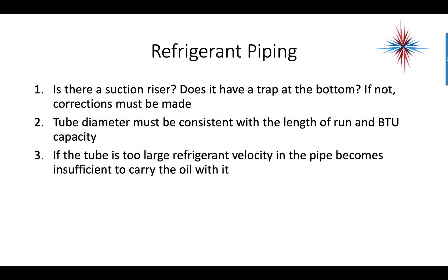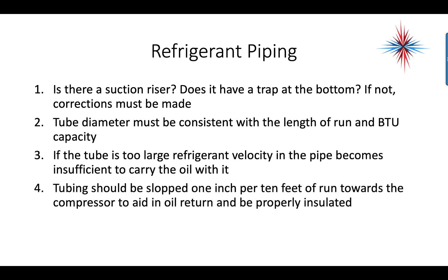If the tube is too large, the refrigerant velocity in the pipes becomes insufficient to carry the oil with it. This is talking about a system without an oil separator. If we are circulating the oil, we're sending it out the liquid line with the refrigerant, through the metering device and the evaporator. If that pipe is too large coming out of the evaporator, we won't have sufficient velocity to force the oil back to the compressor. Tubing should be sloped 1 inch per 10 feet of run towards the compressor to aid in oil return, and it should be properly insulated.